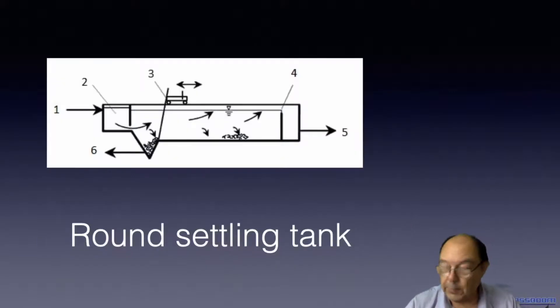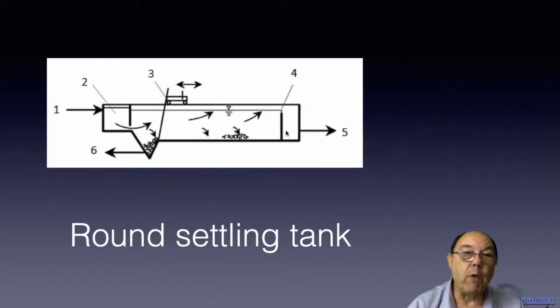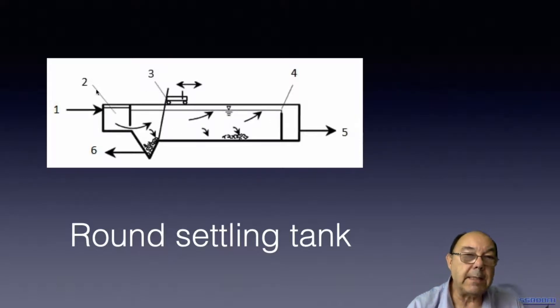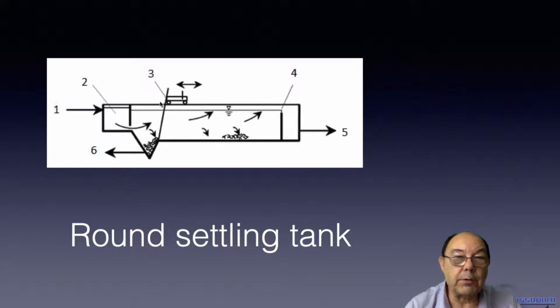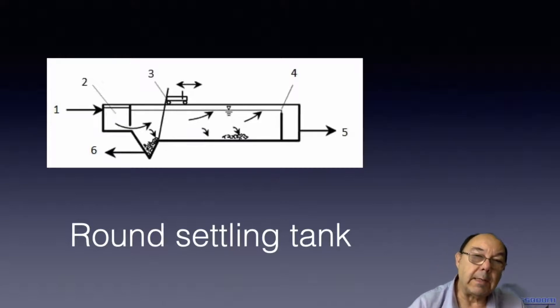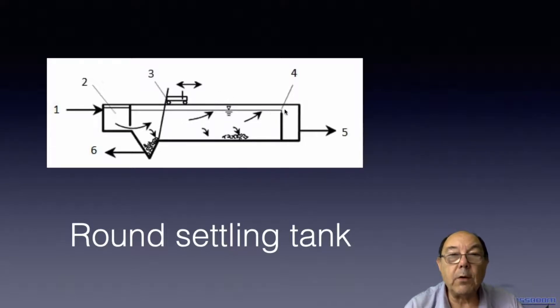This is another type of settling tank — a round one. If you could imagine this is a section through a round tank: this is the centre, so this is the inlet, and this here is the distribution channel. This is the sludge scraper — this thing travels backwards and forwards gathering the sludge and bringing it into the sludge collection point here. This is the overflow weir and here is the discharge point.